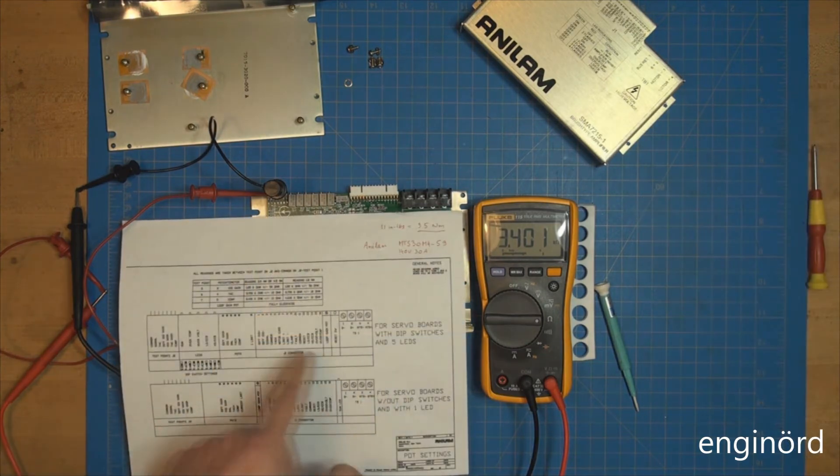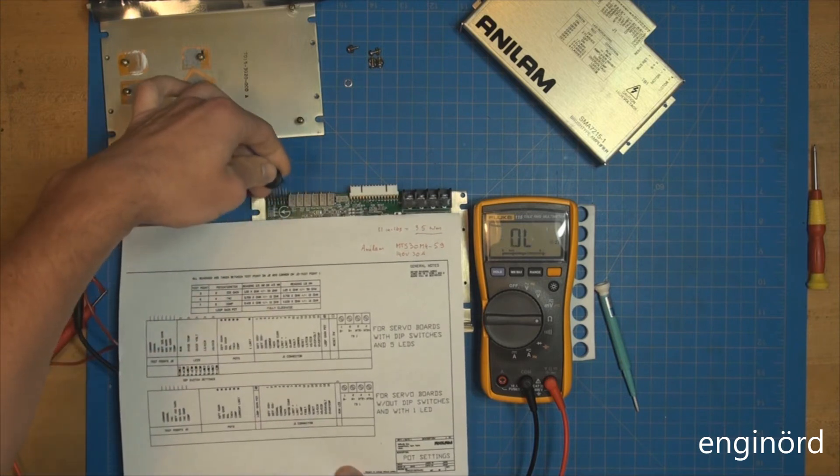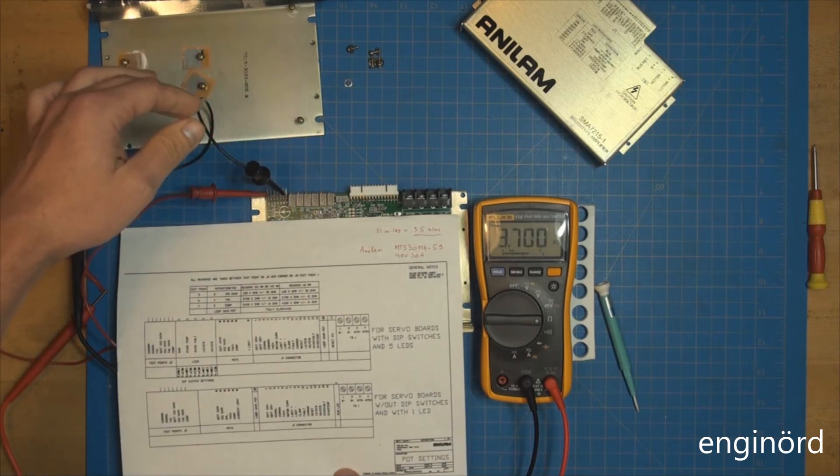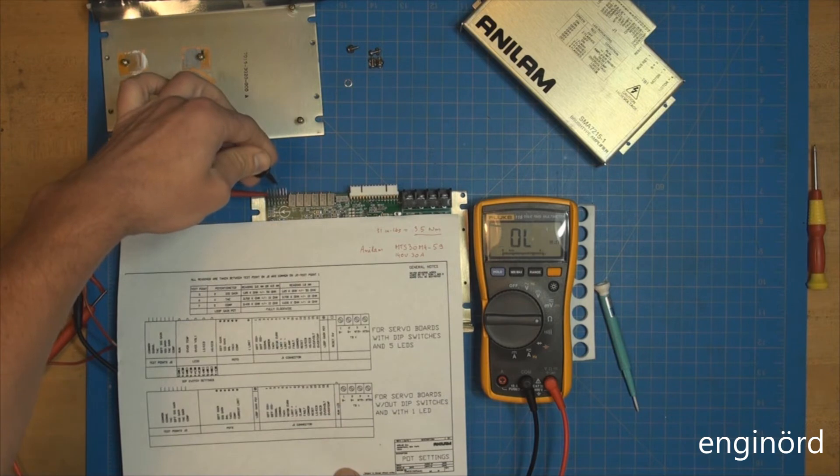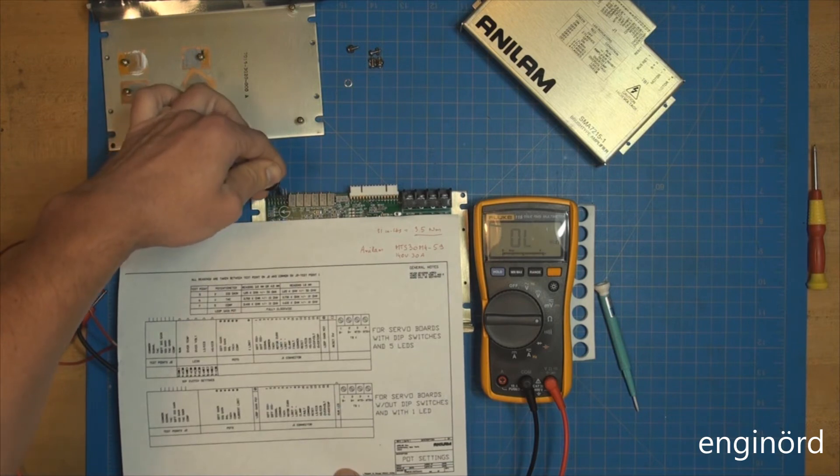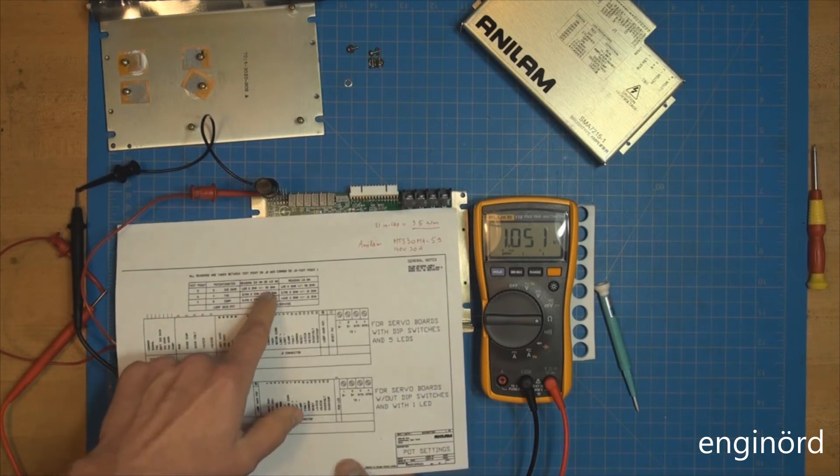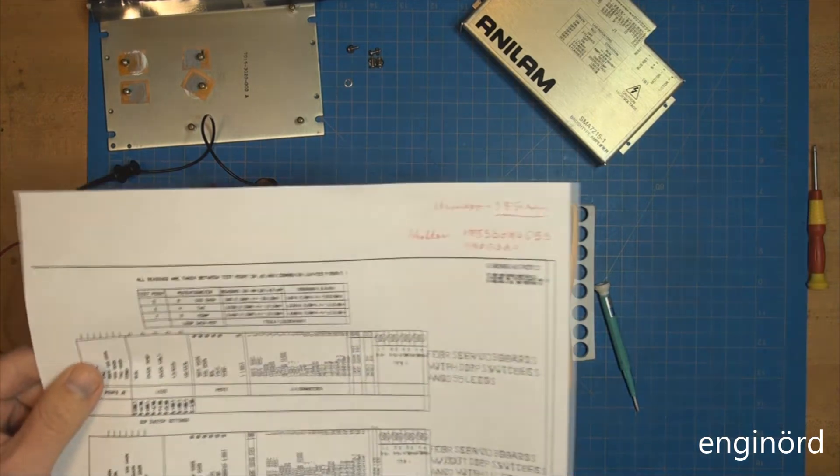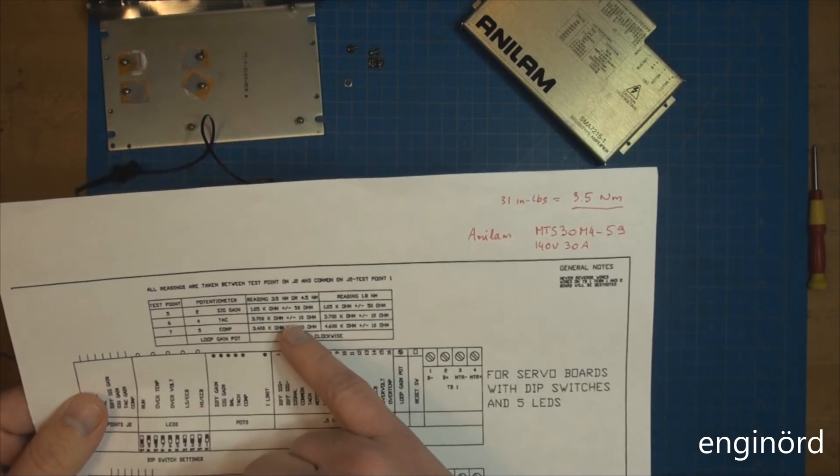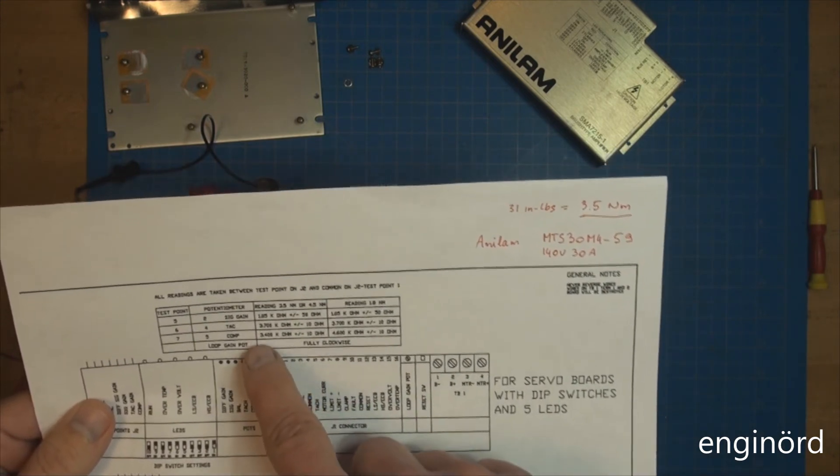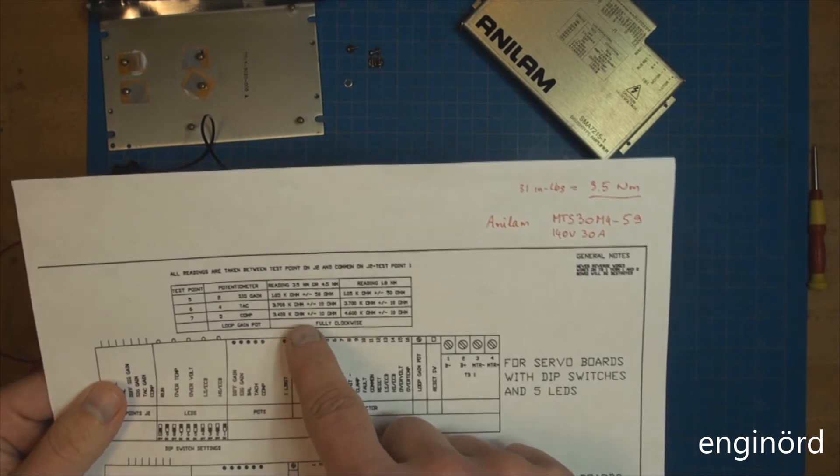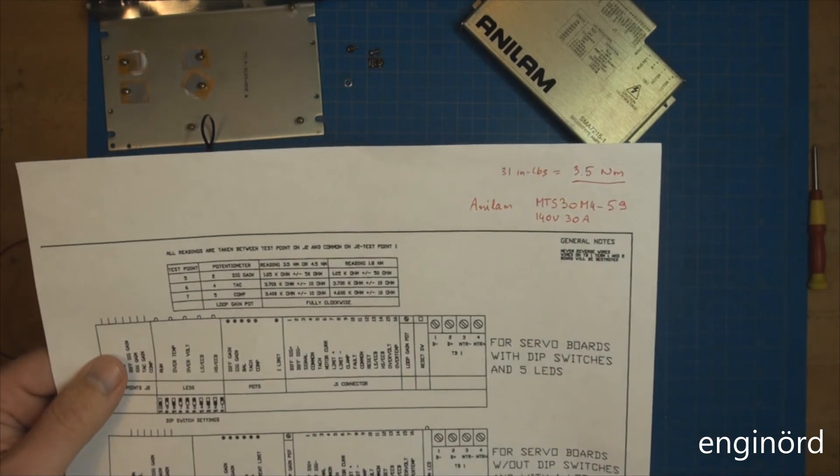We are on test point 7, 3400. Here's test point 6, 3700 right on the money. This is test point 5, and that is 1051. It's supposed to be 1050. There's a tolerance on it - plus minus 50 ohm, plus minus 10 ohm, plus minus 10 ohm. This is 3400 kilohm and the tolerance is 10 ohm, 10 ohm, and 50 ohm. We got it set up.